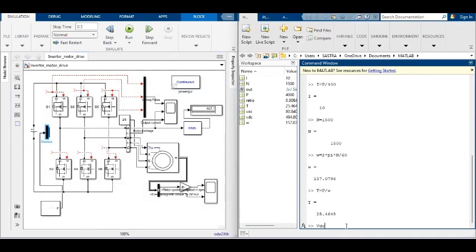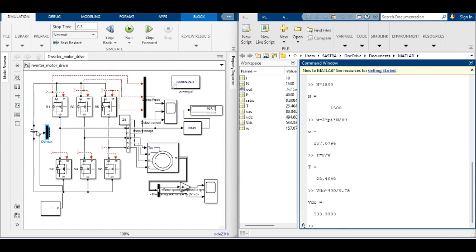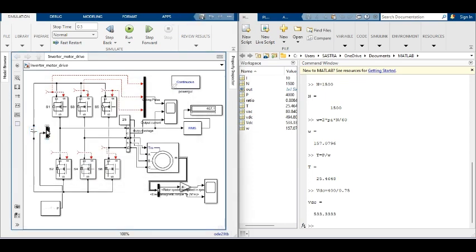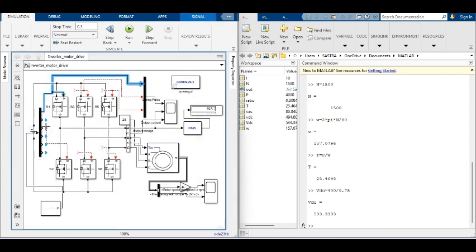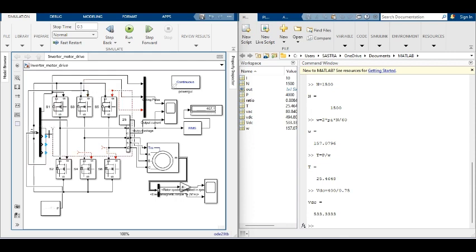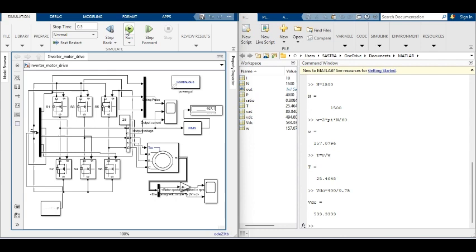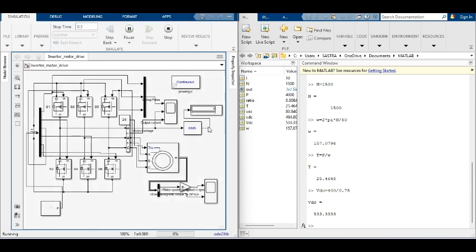First, the rated voltage and frequency are set by utilizing the internally generated PWM options, and the torque speed responses are monitored through the scope. Then voltage and frequency are adjusted to 50% of their rated value by adjusting the reference signal and the corresponding torque speed responses are monitored in the scope.